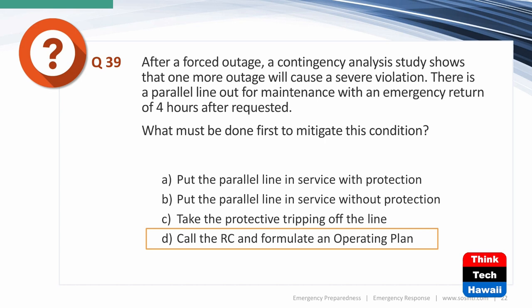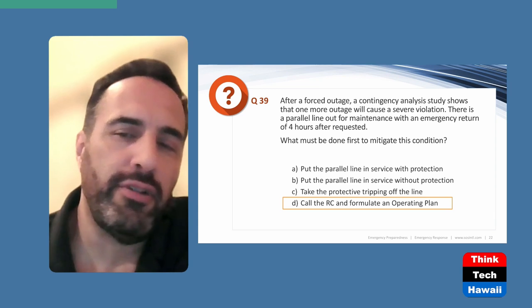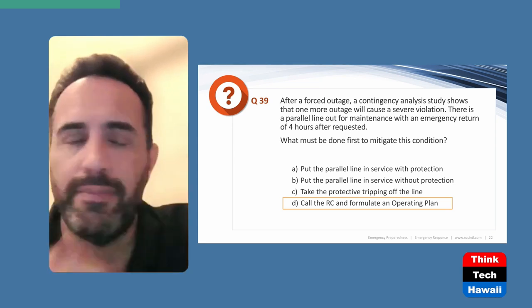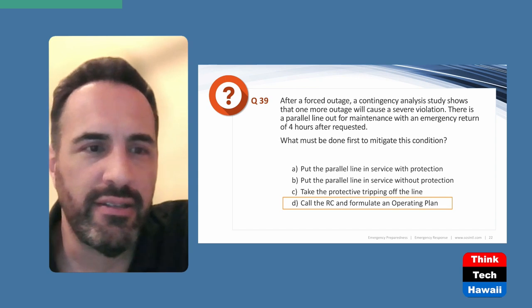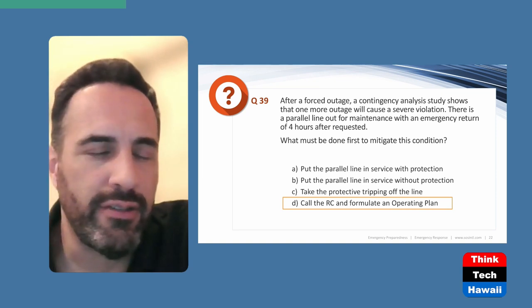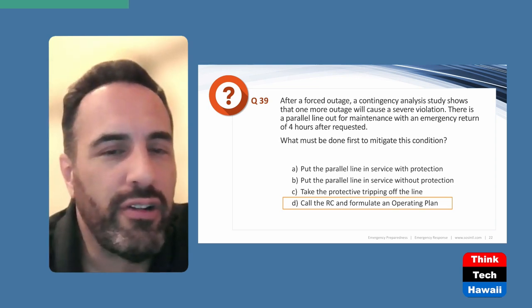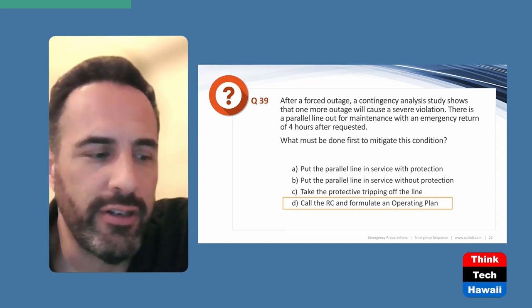Putting the parallel line in service without protection is never acceptable — without protection, a fault would just keep feeding until it burns down. Taking protective tripping off the line is equally bad. The first correct action is to call the RC and come up with an operating plan. They can start working toward getting the line back in service, calling additional crews, or doing some redispatching. Calling the ERC and informing them of this bind is the right first step.